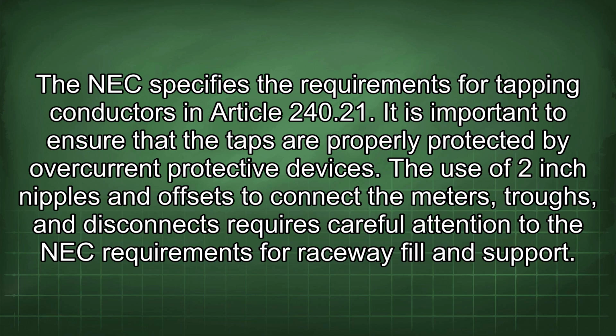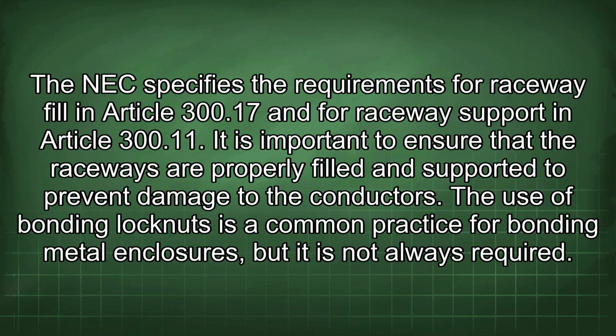The use of 2-inch nipples and offsets to connect the meters, troughs, and disconnects requires careful attention to the NEC requirements for raceway fill and support. The NEC specifies the requirements for raceway fill in Article 300.17 and for raceway support in Article 300.11. It is important to ensure that the raceways are properly filled and supported to prevent damage to the conductors.